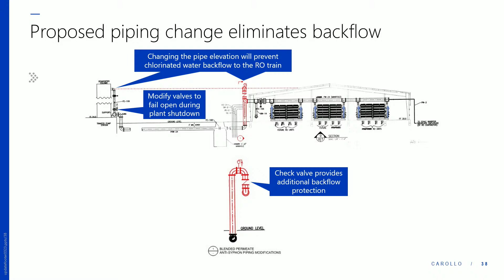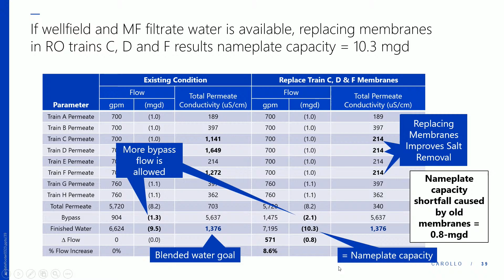If the well field and the MF filtrate water is available, replacing the membranes on trains C, D, and F would result in the nameplate capacity of 10.3 MGD. So for the blended water, again, our goal for salt is 1,376 microsiemens per centimeter. Replacing these three RO trains to a number that mimics some of the other existing trains increases the bypass flow rate from 1.3 to 2.1 million gallons per day, which gives us that nameplate production capacity.